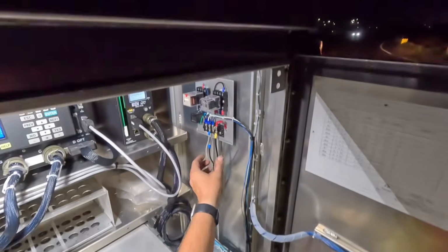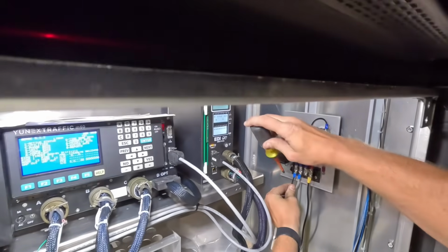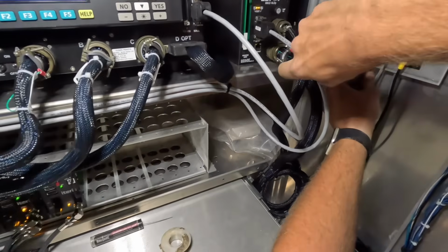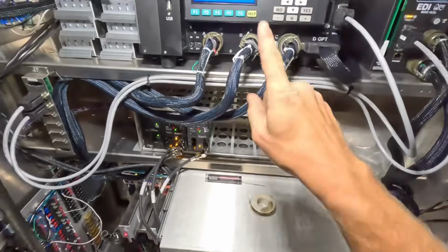They technically ran the red light of the blank out sign, but there's no train, so obviously they can yield like it'd be normal. And now it's locked up like this until the railroad crossing, the train has stopped, and it comes out of the preempt mode. Or on that end of it, when we reland this cable, you'll hear that relay click, and you'll see the controller has already come out of the preemption mode, and it's gonna cycle and work like it should.